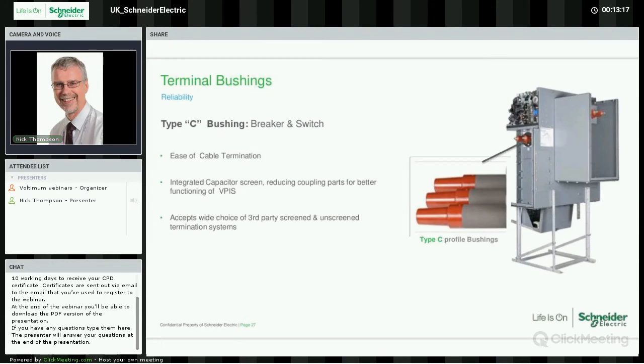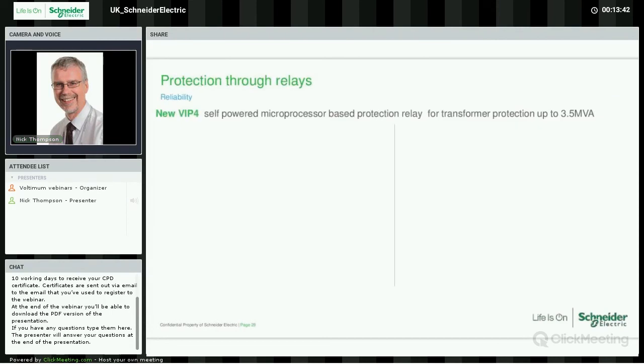The bushing there can be used for termination using a separable screen, or the more traditional heat shrink or cold fit flexible boot. The DNOs are more likely to be moving on to the Type C separable boot because it gives a more reliable termination. With protection relays, this will be there just to protect the transformer.